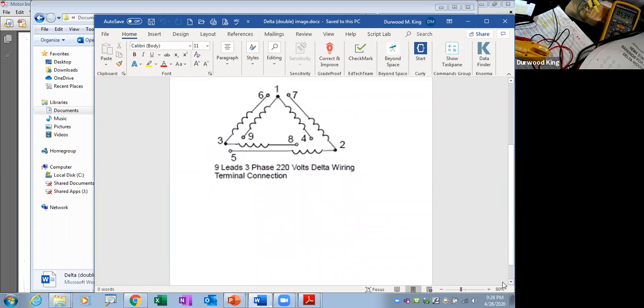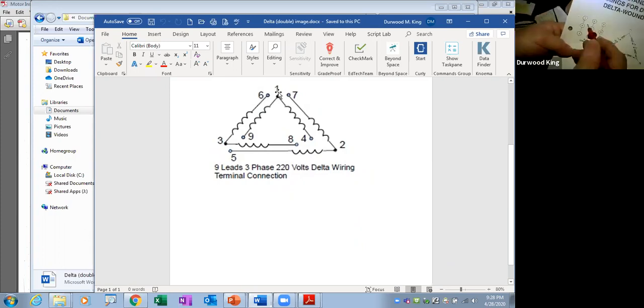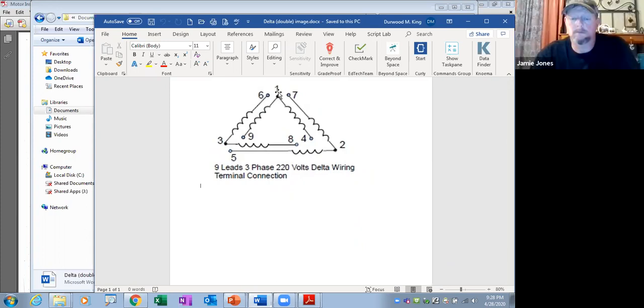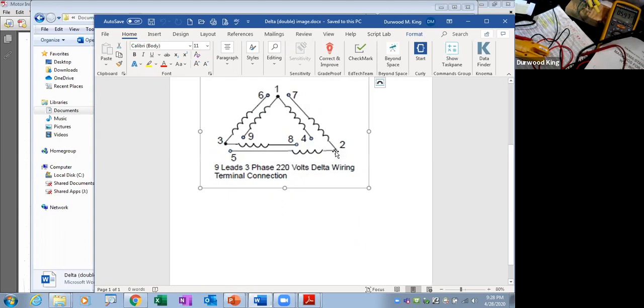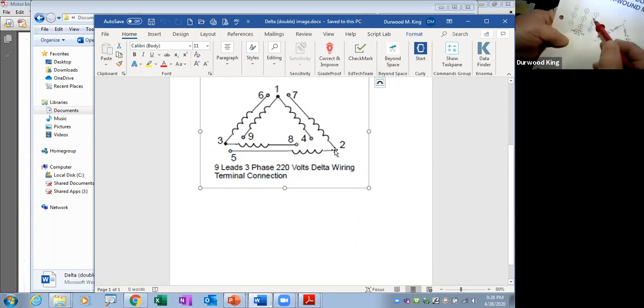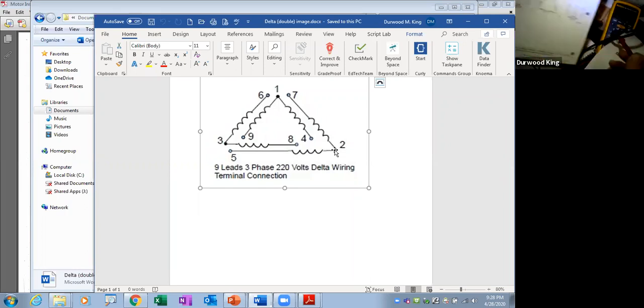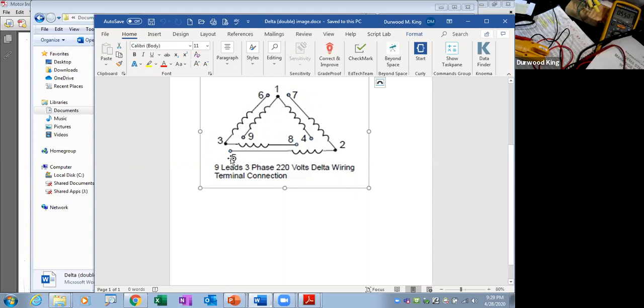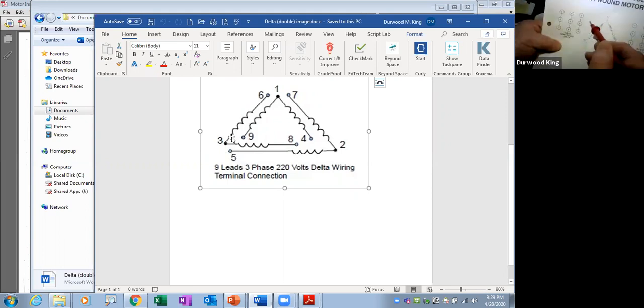You see that? Now, if you look at here, it's got 1, 6, and 7 together. You see that? Now, if you go here on the paper, what do you see here? 1, 6, and 7. You see that? And then down here, you've got 2, 4, and 8 together. All right, look here on the paper. 2, 4, and 8. See that with a wire nut? With the incoming wire, so there's 4 wires per. And then this corner is 3, 5, and 9 that actually go together. So here you've got 3, 5, and 9.